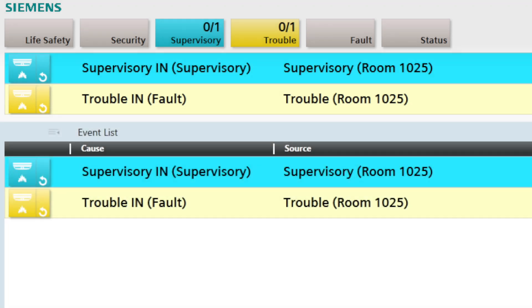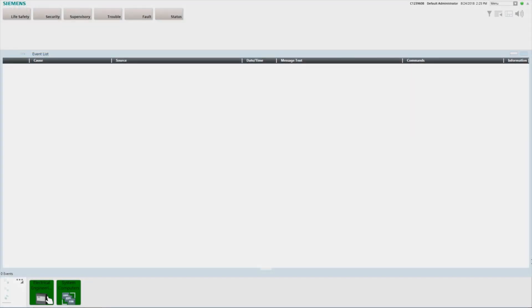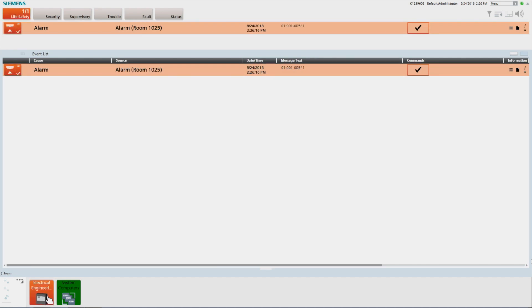First, we have the summary bar, which is located at the top of the screen. It provides constant system status by displaying a summary of the number of events in the system of each type: life safety, security, supervisory, trouble, fault, and status. When a new event is received, the corresponding event lamp will flash and the event count will increase. In addition, the two most important events requiring attention are displayed in the event detail bar just below the event lamps.